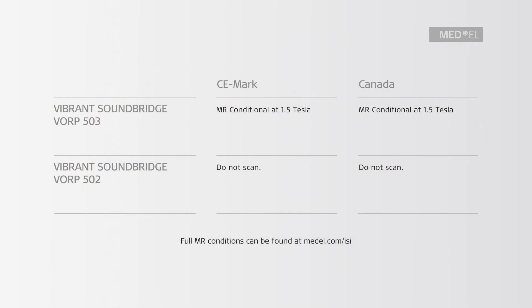With the VORP 503 Vibrant Soundbridge Middle Ear Implant, you can have immediate access to 1.5 Tesla MRI in a few simple steps. By following these basic conditions, your patient can have an easier and more comfortable MRI scan without the need to surgically remove and replace the magnet. Patients with the VORP 503 Implant may be safely scanned without magnet removal at 1.5 Tesla, following the conditions described in the instructions for use.